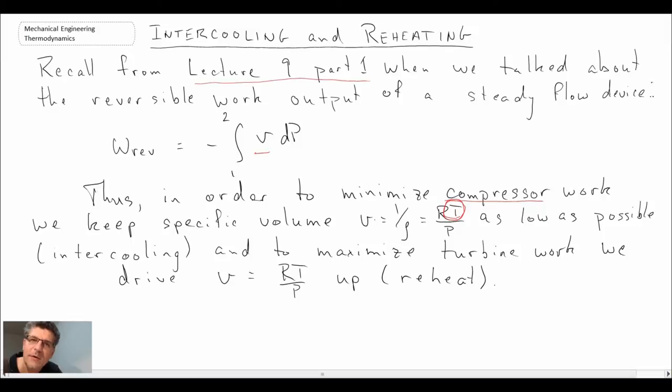The way that you can minimize the specific volume is by playing with the temperature. If you move the temperature down or cool the gas, then that will minimize the amount of work you're doing in compressing. That brings in the idea of intercooling.